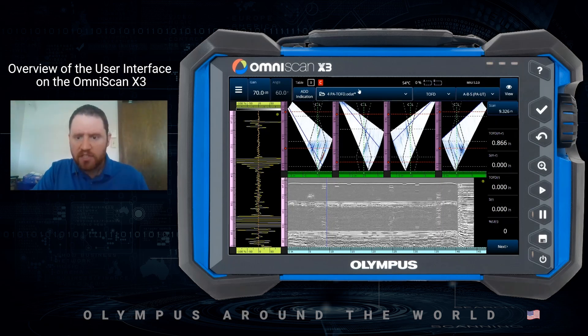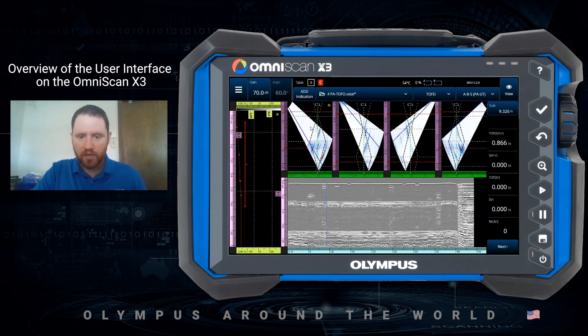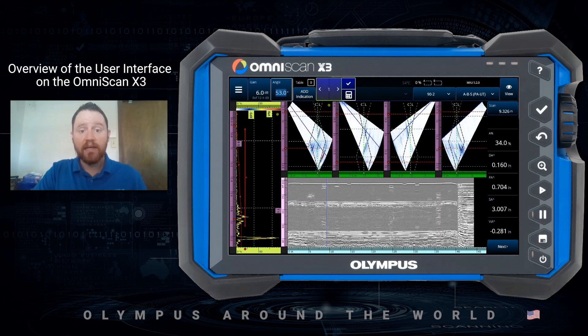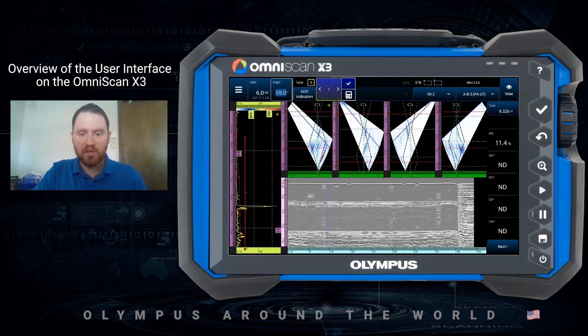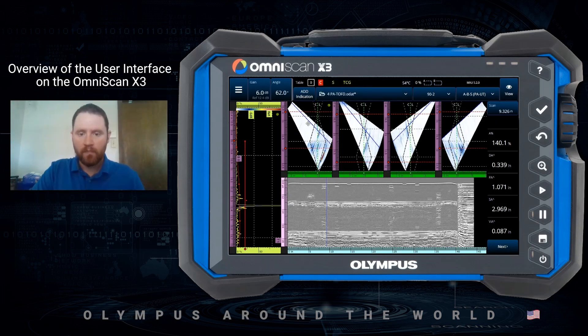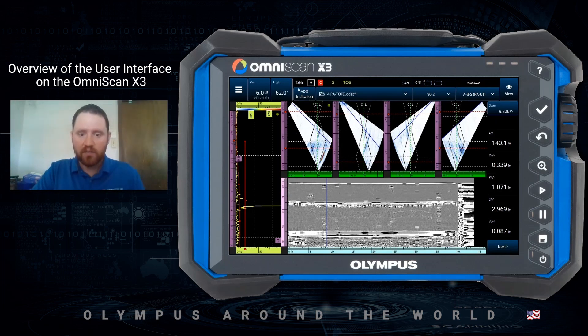Moving along the top, I also have access to my angle. So if I were to select one of my phased array channels and switch to that group, I can grab the angle from that display and adjust its position during analysis or during setup if I'm working on a new file or a new calibration. We can also see a shortcut for adding indications into the table.